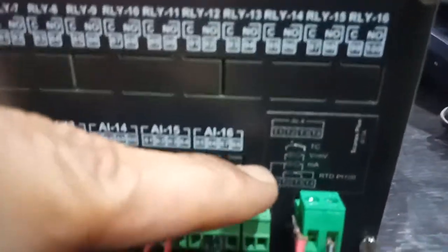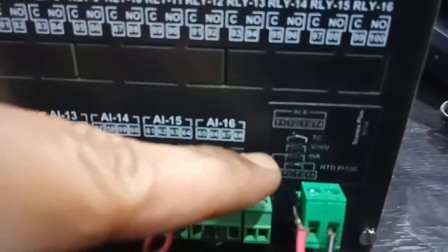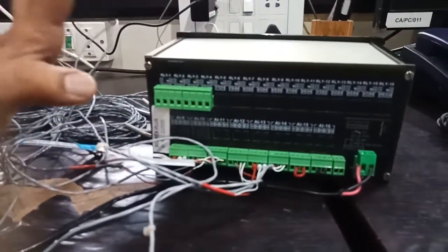Here you can see the wiring diagram of each terminal. For example, if you want to connect the PT100 sensor, milliampere, thermocouple, and millivolt. It has four alarm relay outputs for each channel. Whenever the channel's particular PV value goes in the alarm mode, the relay output will turn on.